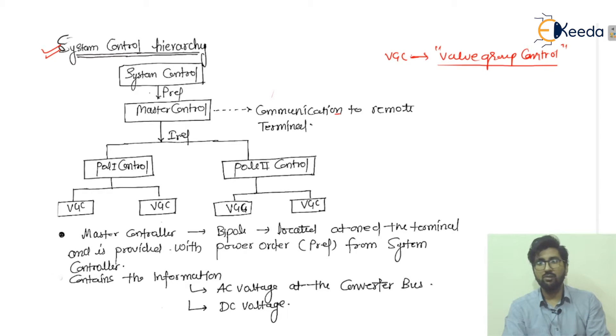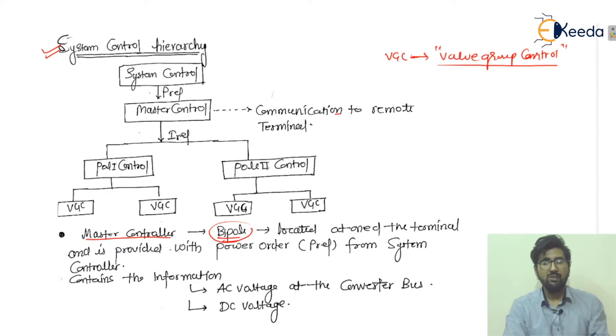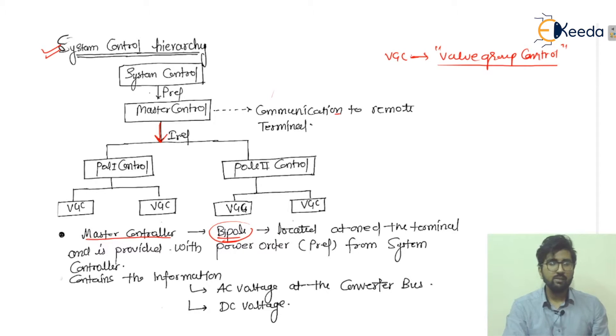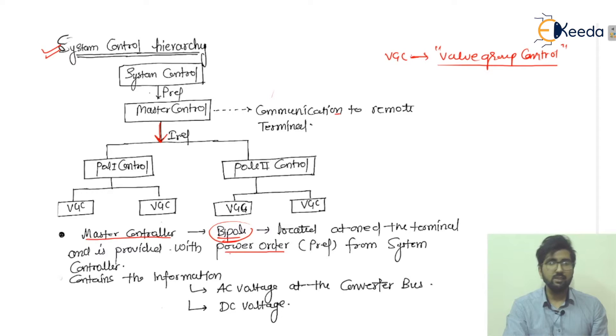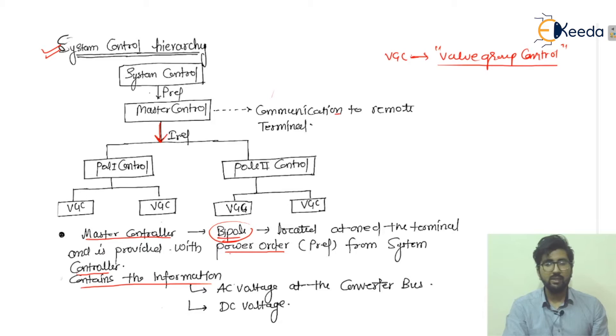Now let's talk about what the master control actually does. The master control provides the bipole — it provides the I_ref, that is the reference current, for pole one control and pole two control. The master control is located at one of the terminals and is provided with the power order, P_ref, that is the reference power from the system control.